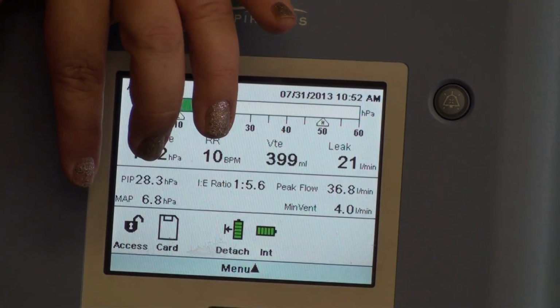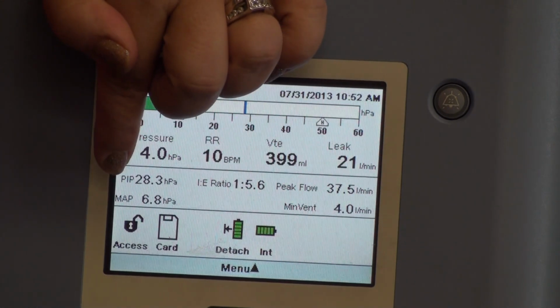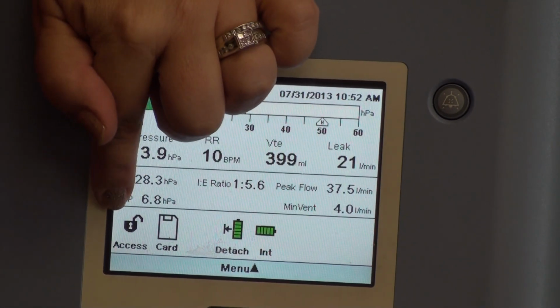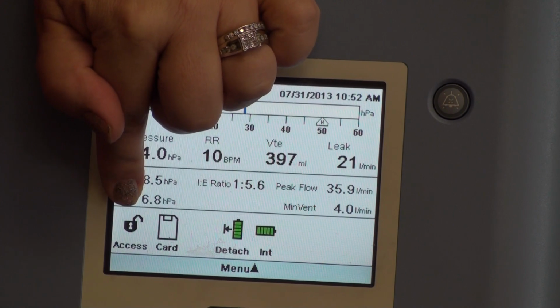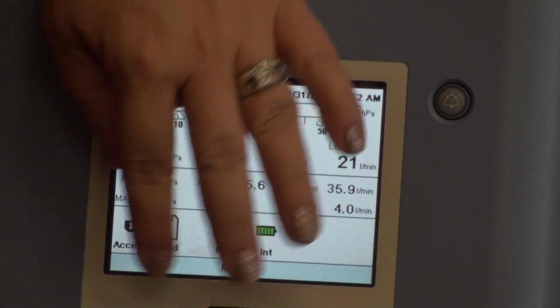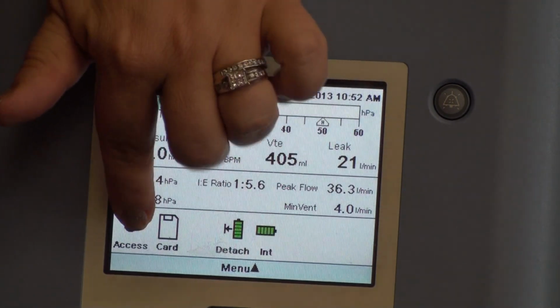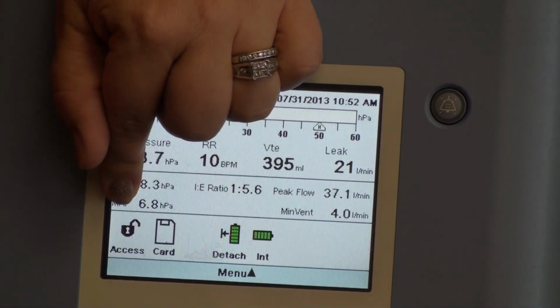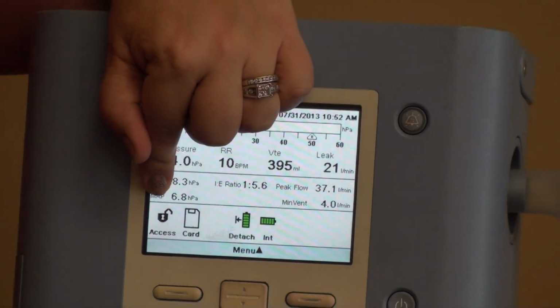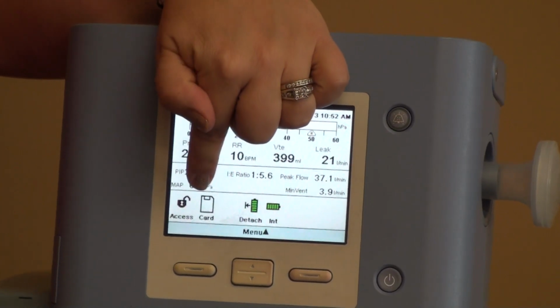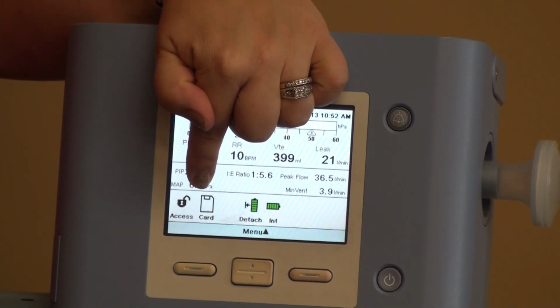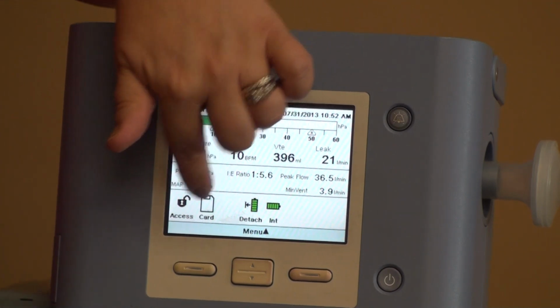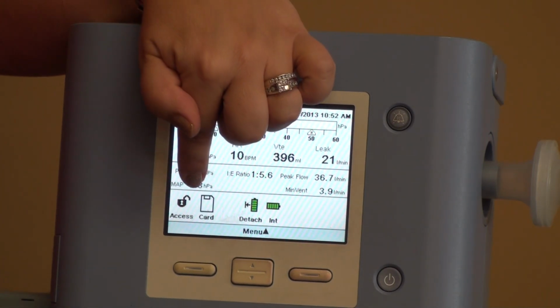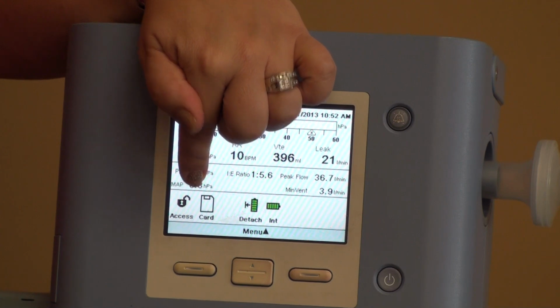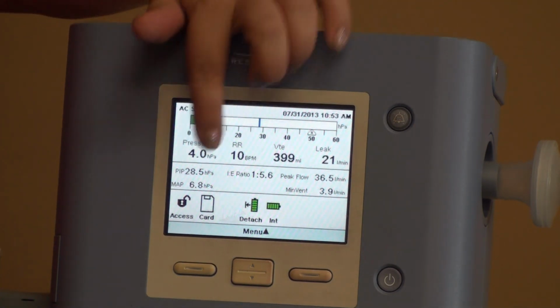So if you refer to your slide in your packet, first of all, you're going to have your full menu access. This is kind of confusing to people also because this has nothing to do with locking out your keypad. Clients, if this is unlocked here, that doesn't mean that clients can get in here and make changes. What it means is you have full access to make changes of whatever is prescribed by the physician. The next one over is going to be your card. That just means that my card is in place, my SD card is in place and recording my data. If it had an X over the top of it, that just means there's something wrong or it's not in there, something's not working right, but it still runs the ventilator just fine. It's just not recording the data.